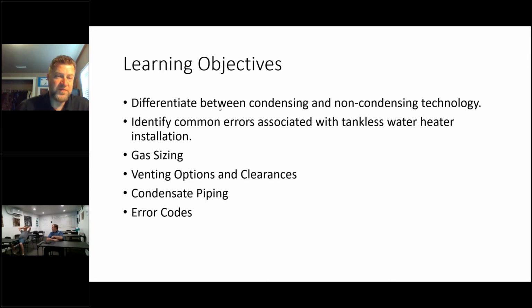So today we're going to be learning the differences between condensing and non-condensing technology. We'll be identifying common errors associated with tankless water heater installs. One of the biggest things that we see in the field that doesn't get installed properly is the gas sizing, so we'll be covering that as well. The venting options and clearances for the National Fuel Gas Code, condensate piping and how it needs to be piped through condensing water heaters, and then we'll go over error codes and how to fix error codes.